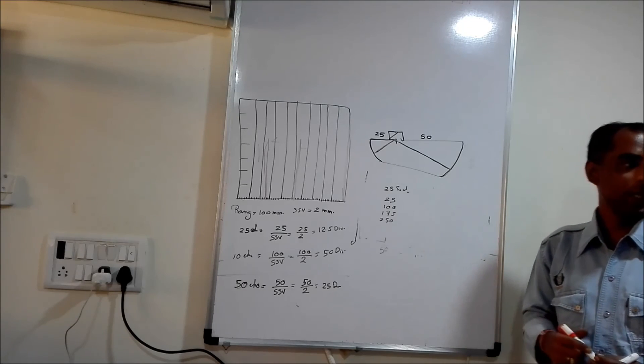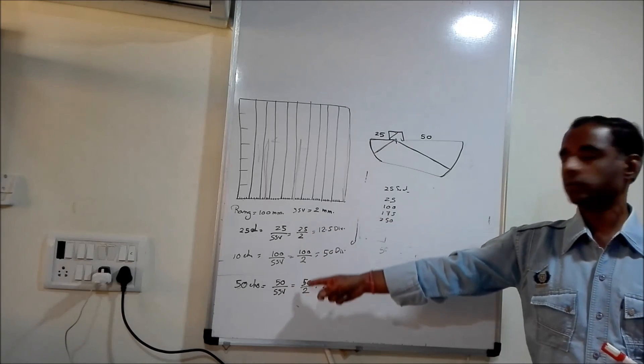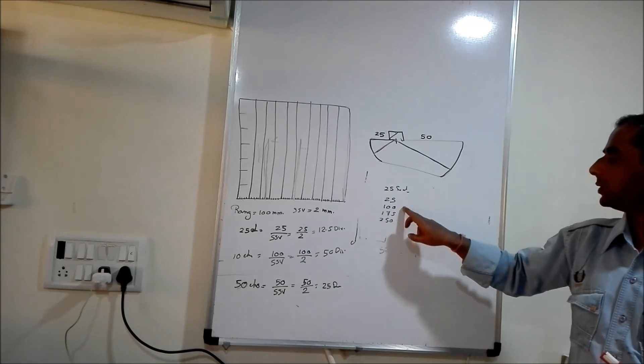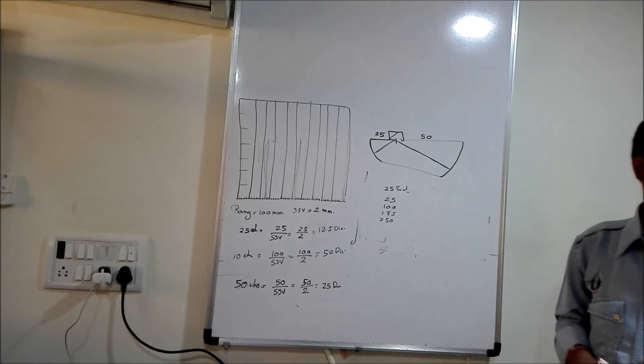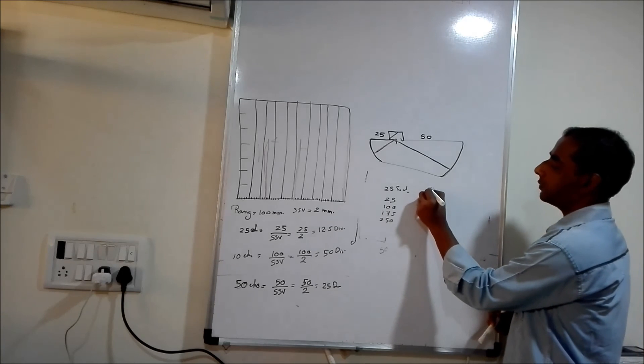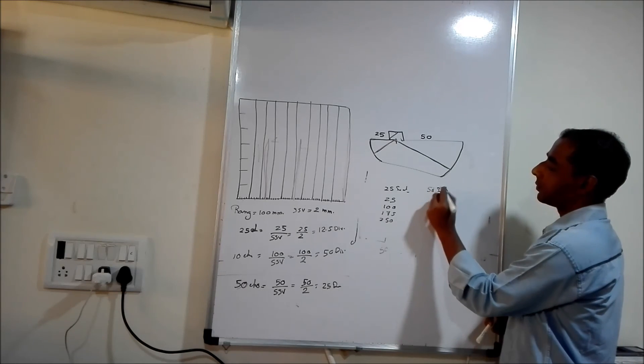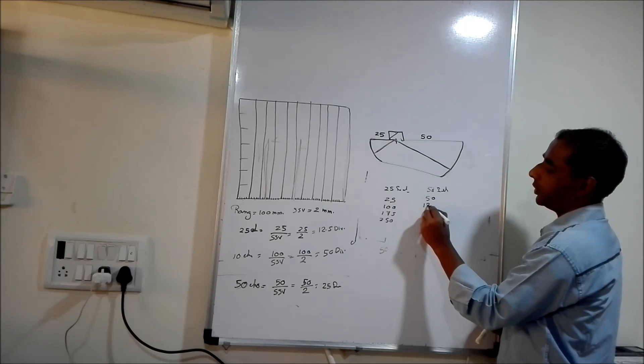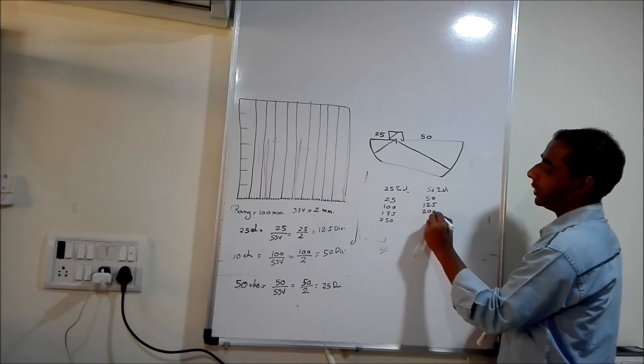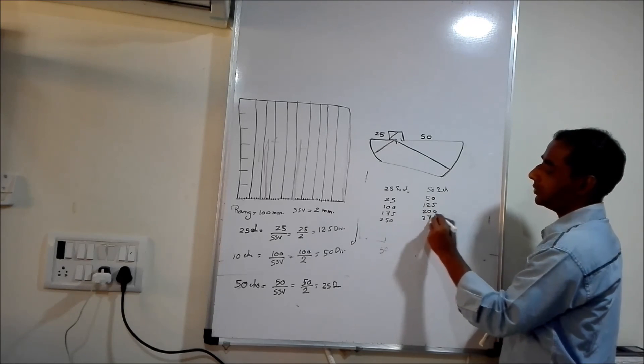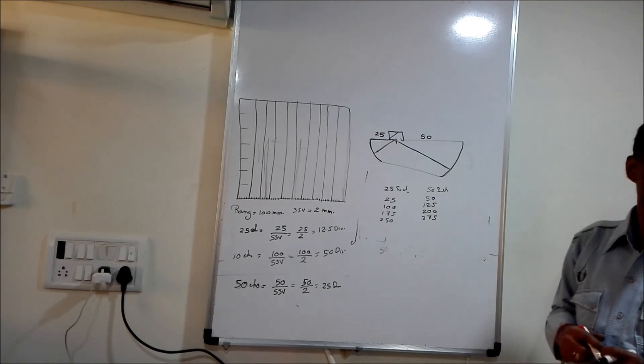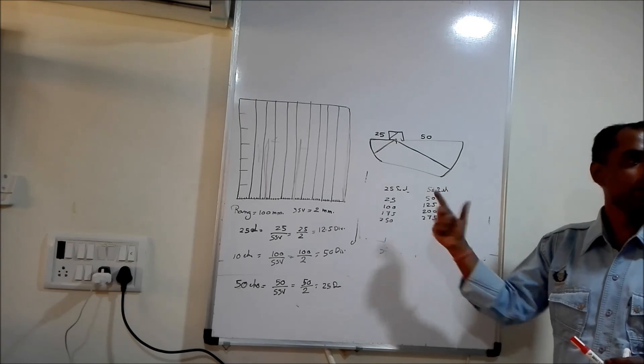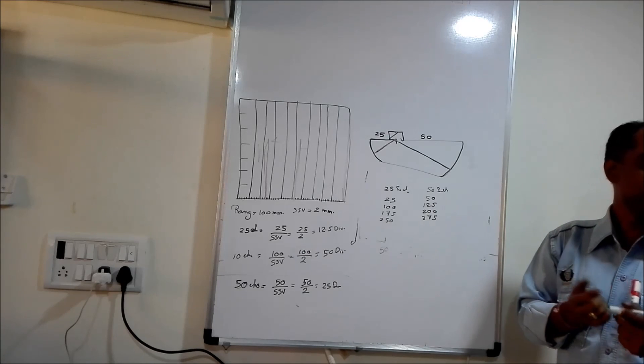So for calibration output, just divide by SSV — divide by SSV and you will get the number of divisions. Same if I am going for the 50 side: first echo at 50, then 125, 200, 275 and so on. So you can cross-verify by rotating the probe.